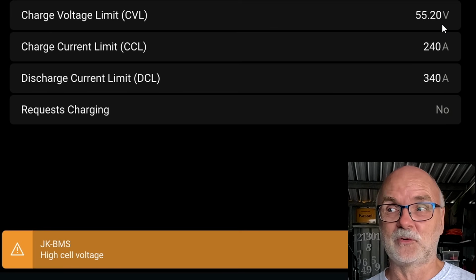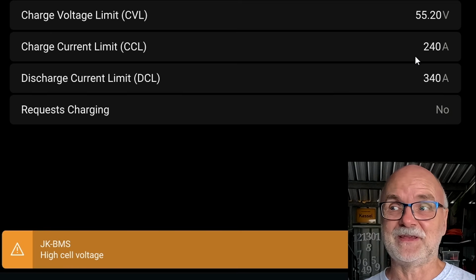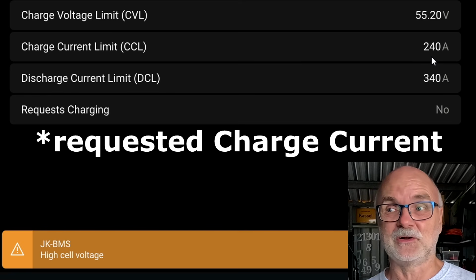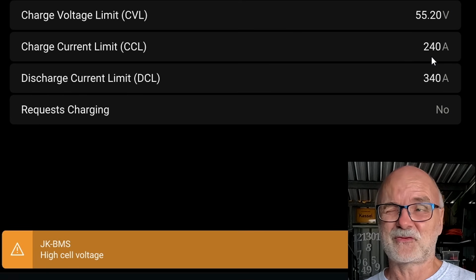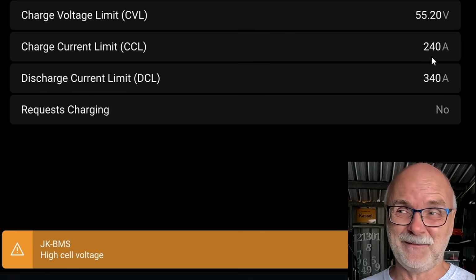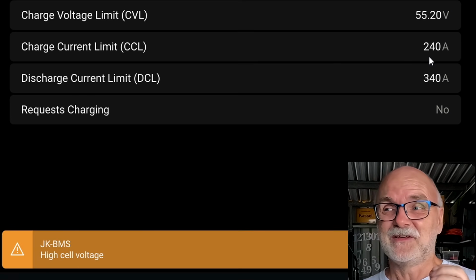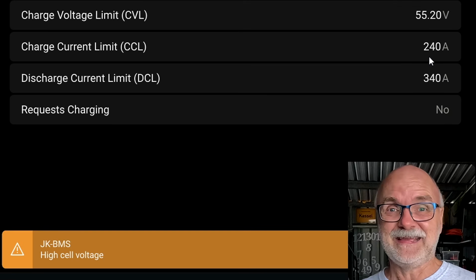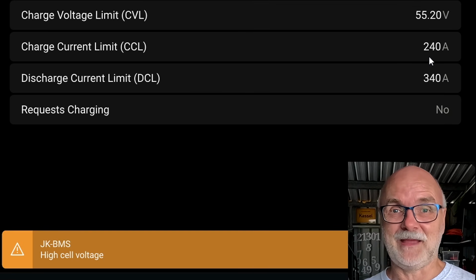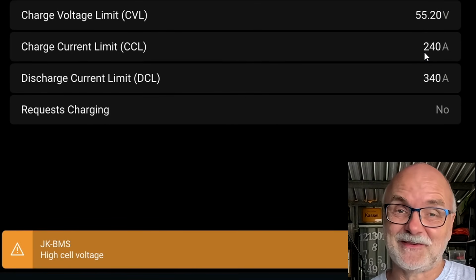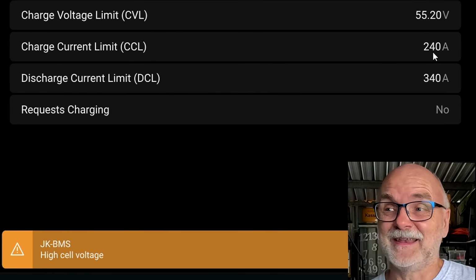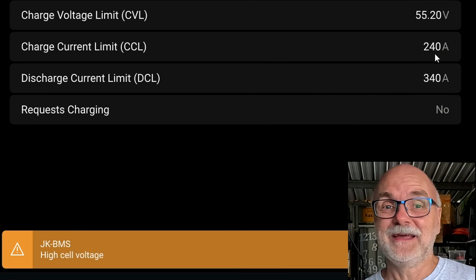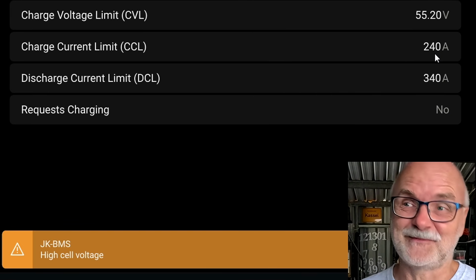voltage of 55.2 volts, but you can also see now the requested charge current has now reduced from 340 amps, I think, to only 240 amps. Yeah, it has taken away 100 amps of the faulty BMS. That is of course total nonsense, because we had 320 amps requested before and now we have 240 amps only. So it has only detected 80 amps, not 100.